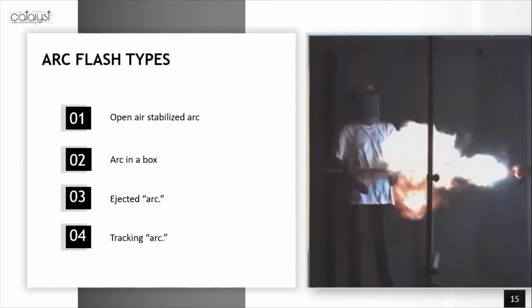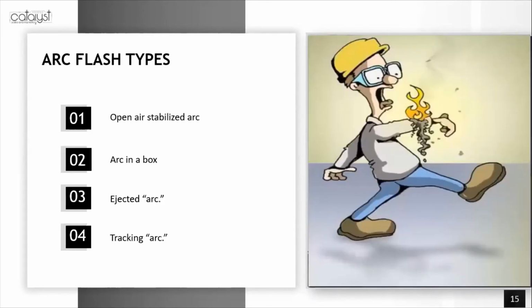Ejected arc, although rare, I mean, even myself in industry, I've seen twist locks blow off 30 amp, and not quite to this extent, but I've seen it. And the other one would be tracking arc. Although rare, it can happen. And the tracking arc is where the flash occurs between air and moisture on your clothing and skin, and the tracking arc goes up in your clothing. It can cause ignition of clothing, and this usually happens under higher voltages.